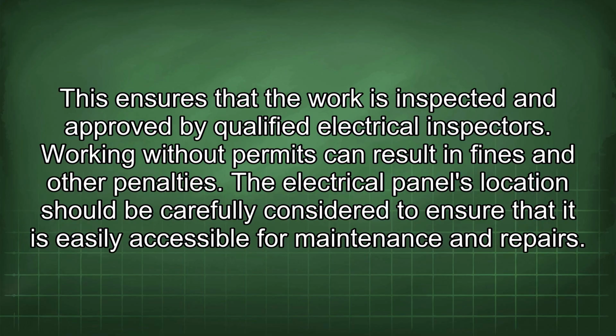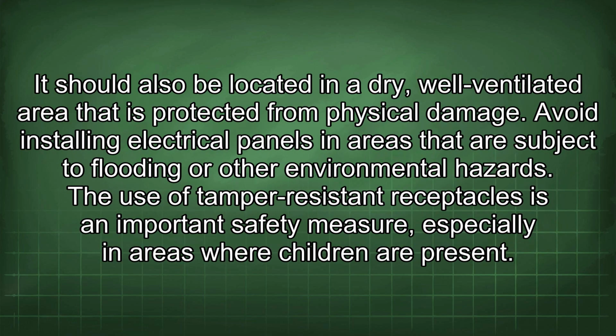The electrical panel's location should be carefully considered to ensure that it is easily accessible for maintenance and repairs. It should also be located in a dry, well-ventilated area that is protected from physical damage. Avoid installing electrical panels in areas that are subject to flooding or other environmental hazards. The use of tamper-resistant receptacles is an important safety measure, especially in areas where children are present.